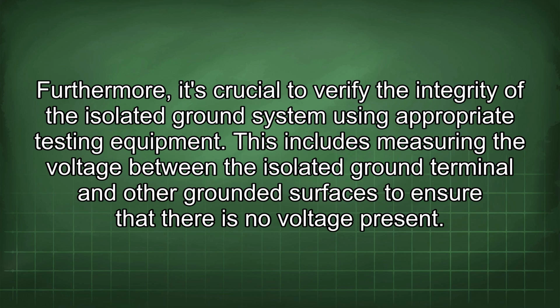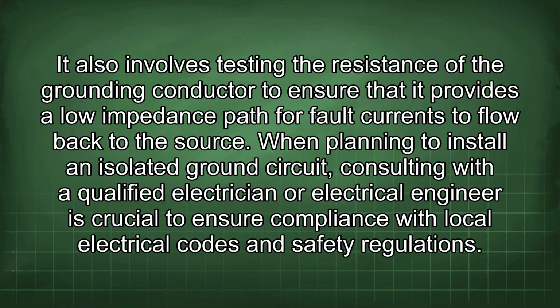Furthermore, it's crucial to verify the integrity of the isolated ground system using appropriate testing equipment. This includes measuring the voltage between the isolated ground terminal and other grounded surfaces to ensure that there is no voltage present. It also involves testing the resistance of the grounding conductor to ensure that it provides a low impedance path for fault currents to flow back to the source.